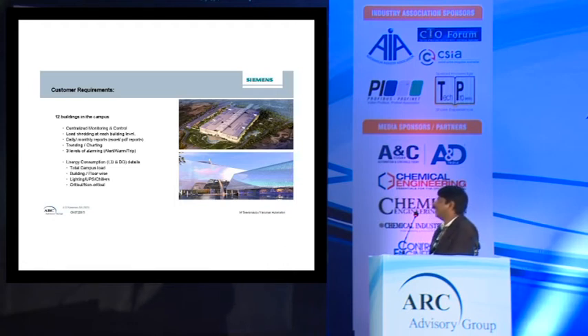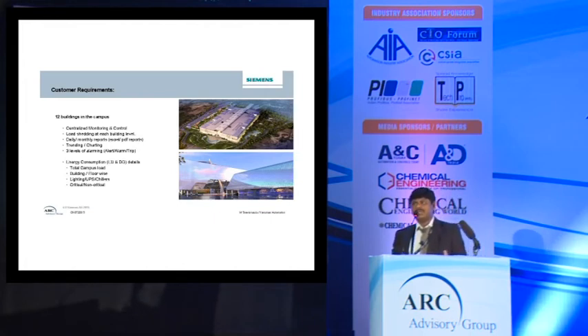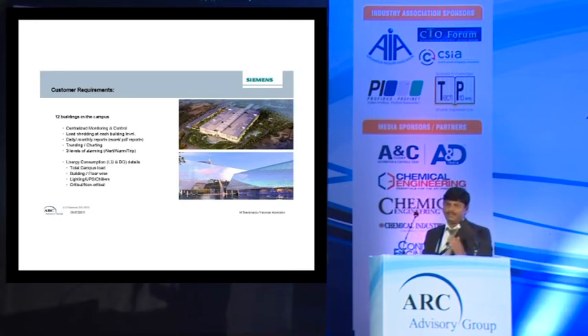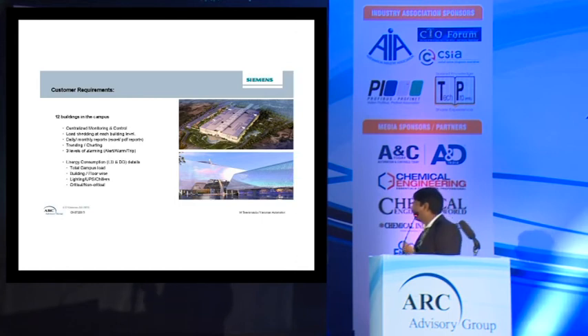Here again, alarming - like when you trip the breaker, before that they wanted alarms, three levels of alarming. For example, say your demand is 10 MVA. If you've crossed 8 MVA, give an alert saying you've crossed so-and-so. If it crosses 9 MVA, give an alarm saying it's going to trip soon - almost 90% of your energy crossed. Then when it crosses 100%, 10 MVA, immediately trip the breaker.